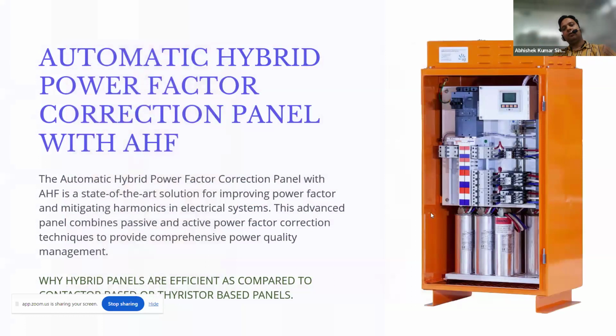Then basically we have automatic hybrid panels, correction panels. What is this? With the capacitor we put a contactor and it is controlled by the active filter. So this is basically a combination. You may say it is not completely an active filter panel. This is partial active filter and partial passive. It will reduce the cost of the panel, because active filters are quite costly, and we have to make it cost efficient also. If you want a cost efficient as well as effective system which can work very fast, this is the best solution to have nowadays: we can have the capacitor with contactor and place the active filter with that.